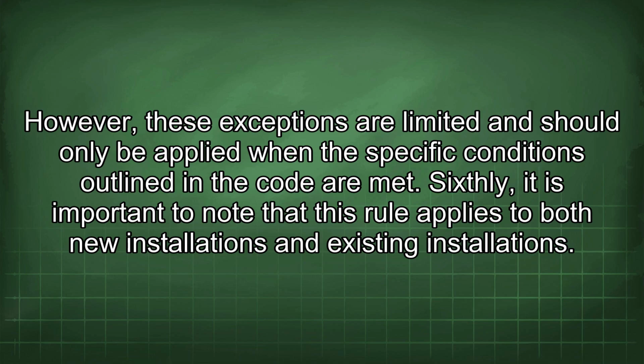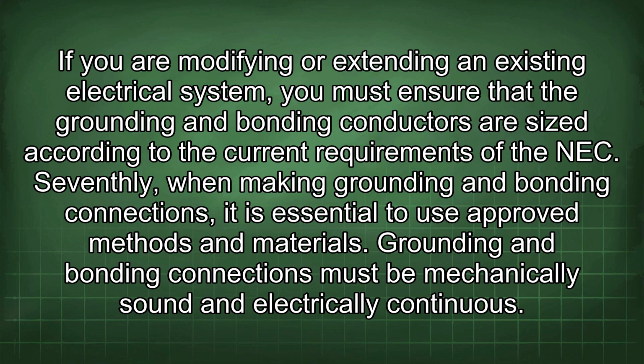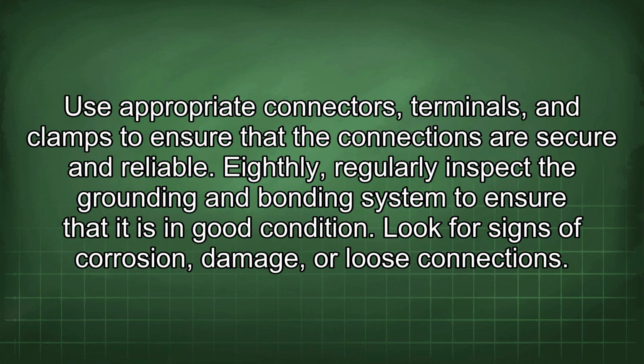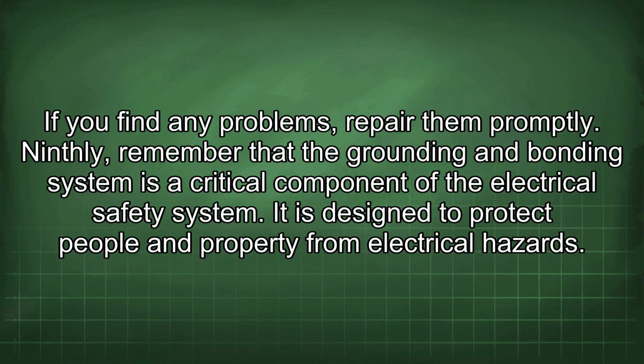Sixthly, it is important to note that this rule applies to both new installations and existing installations. If you are modifying or extending an existing electrical system, you must ensure that the grounding and bonding conductors are sized according to the current requirements of the NEC. Seventhly, when making grounding and bonding connections, it is essential to use approved methods and materials. Grounding and bonding connections must be mechanically sound and electrically continuous. Use appropriate connectors, terminals, and clamps to ensure that the connections are secure and reliable. Eighthly, regularly inspect the grounding and bonding system to ensure that it is in good condition. Look for signs of corrosion, damage, or loose connections. If you find any problems, repair them promptly.